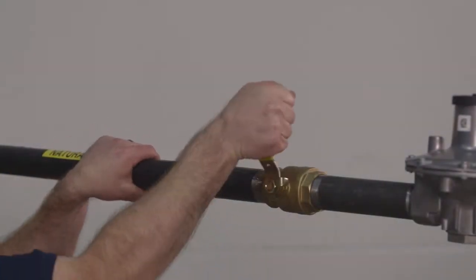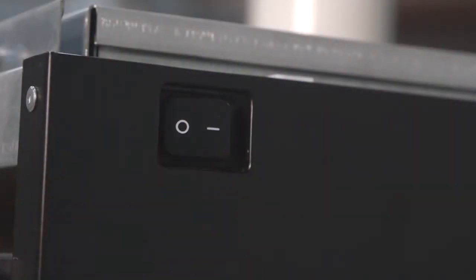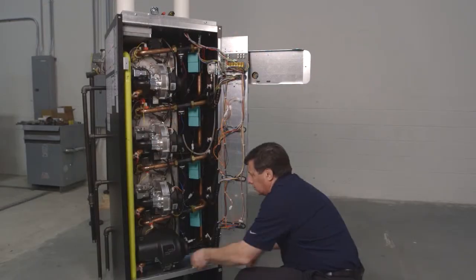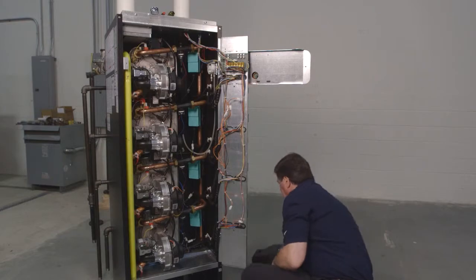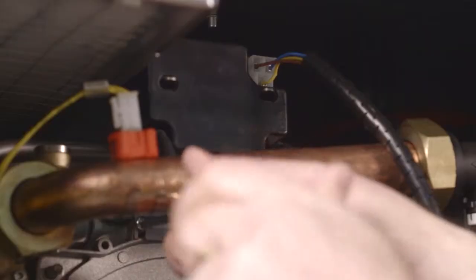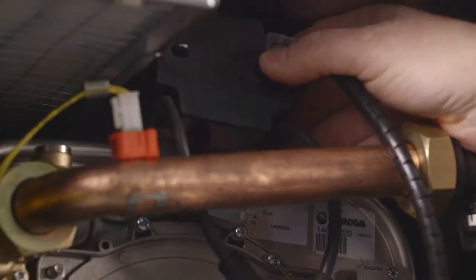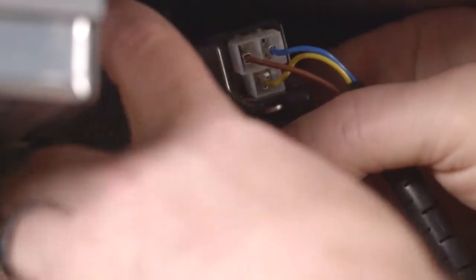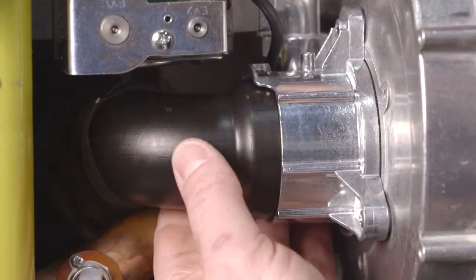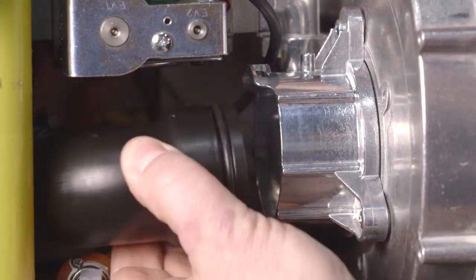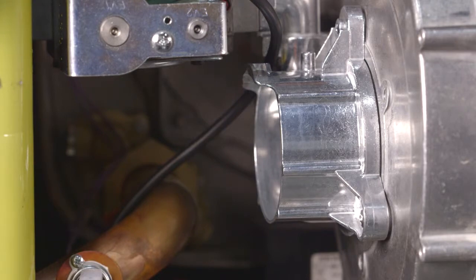Close the manual shutoff valve. Turn off the unit. Remove the unit covers. Loosen the screws and move up the ignition transformer. Disconnect the 2 wires from the ignition electrodes. Remove the electrical connections from the ignition transformer and remove the ignition transformer. Then, disconnect the wire from the flame detection electrode. Rotate the air inlet in the down direction. Pull the air inlet silencer in the left direction and remove it from the fan.